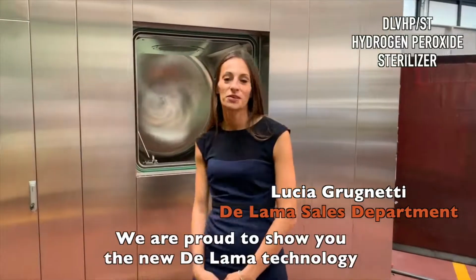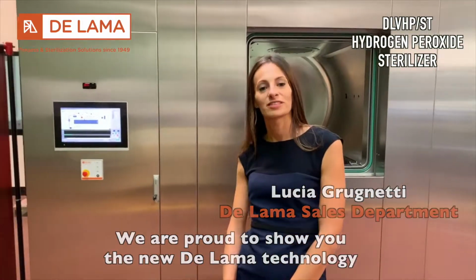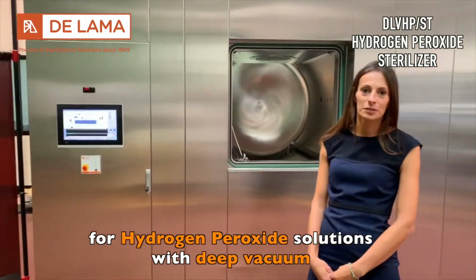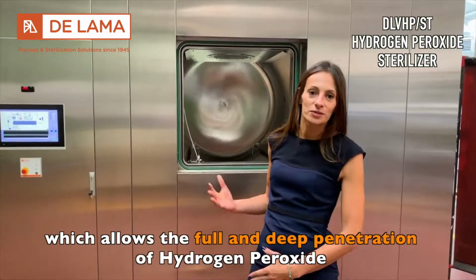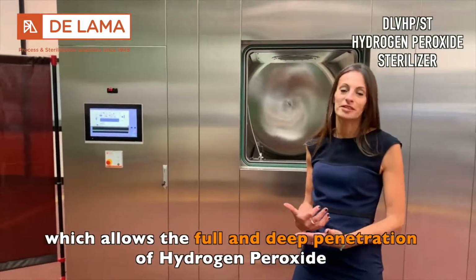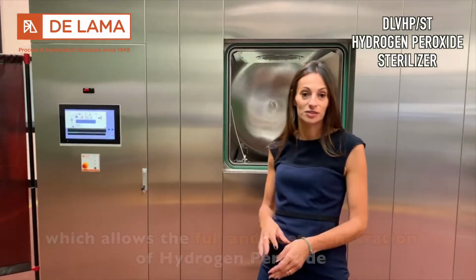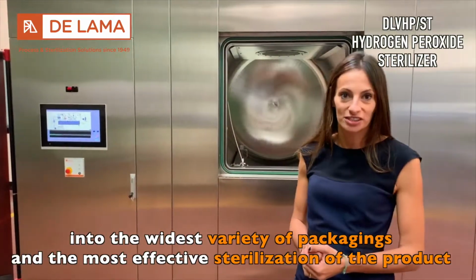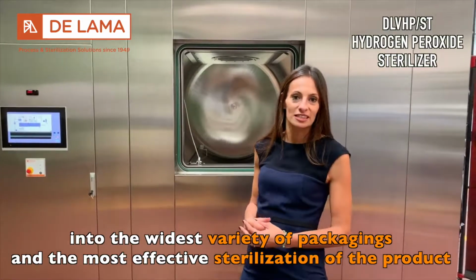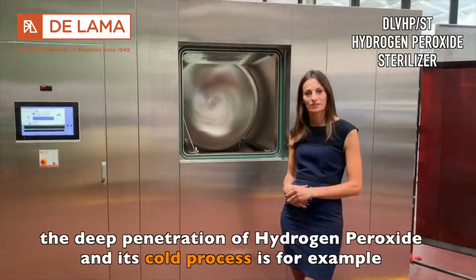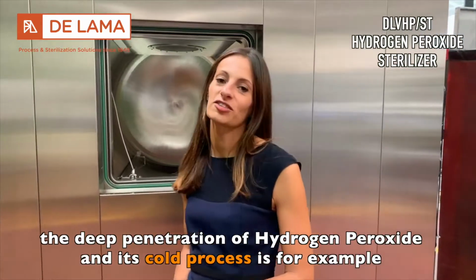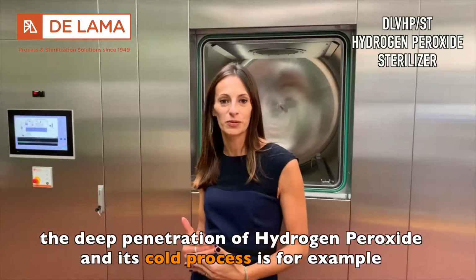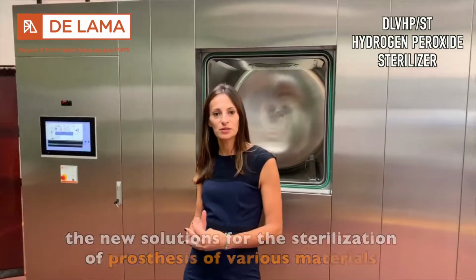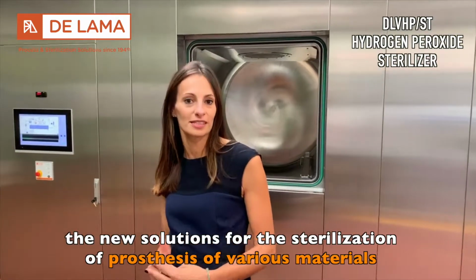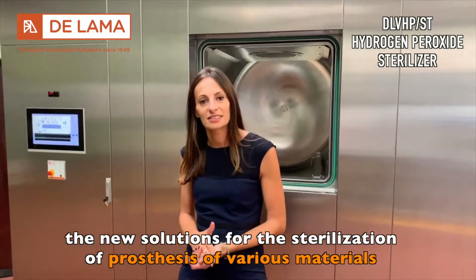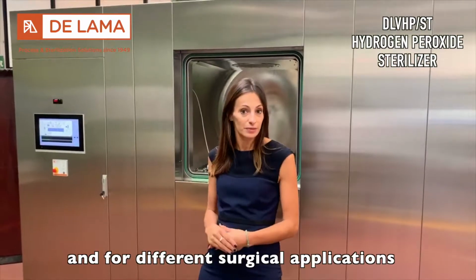We are proud to show you the new De Lama technology for hydrogen peroxide solution with the deep vacuum technology, which allows the full penetration and the deeper penetration of hydrogen peroxide into the widest variety of packaging and the most effective sterilization of the product. The deeper penetration of hydrogen peroxide and its cold process is, for example, the new solution for the sterilization of prosthesis of various materials and for different surgical applications.